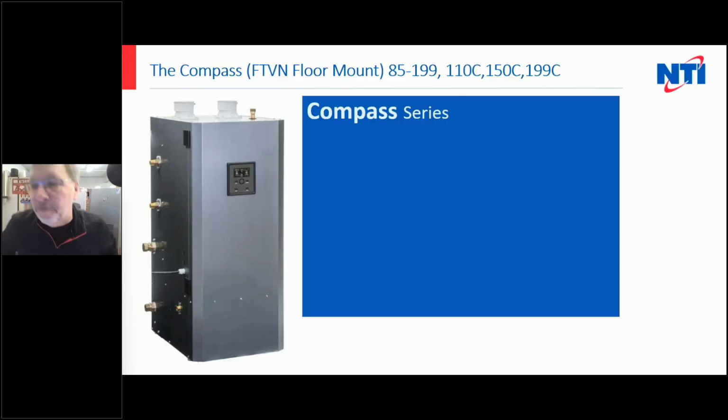And here's what I wanted to get to. Hopefully you like the FTVN and you like the fire tube. I like water tubes. I like the way they resist crappy water better than a fire tube. I like the lack of maintenance that you have to do on a fire tube.